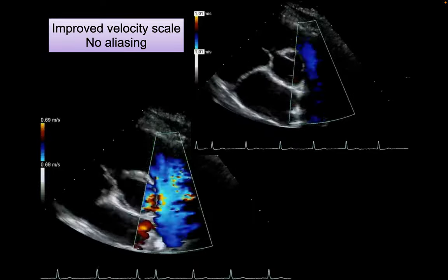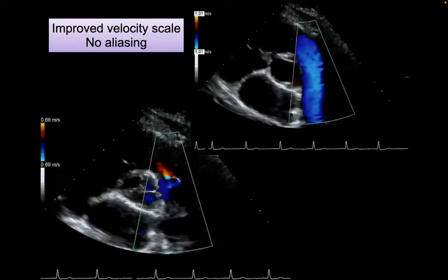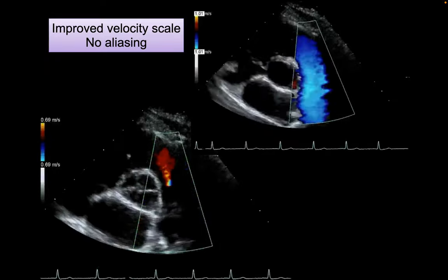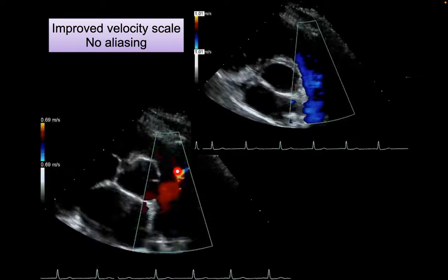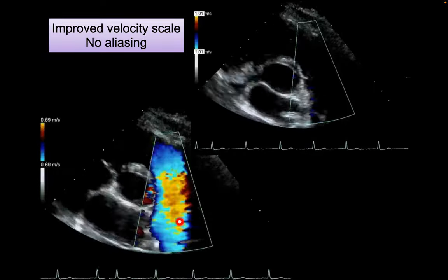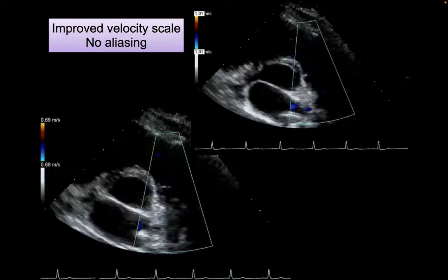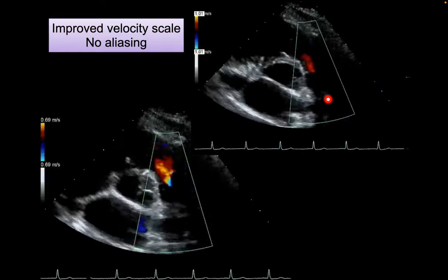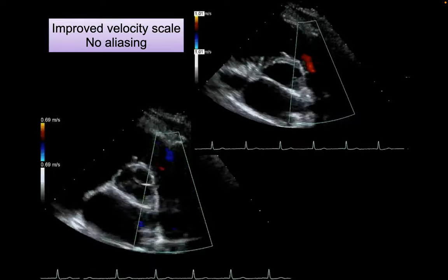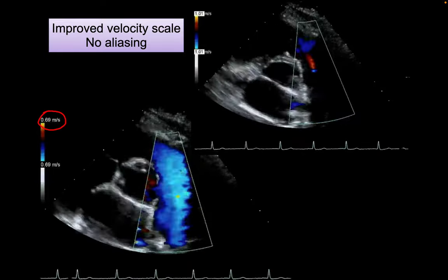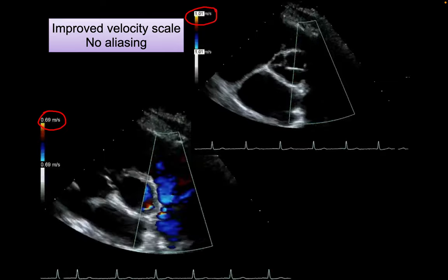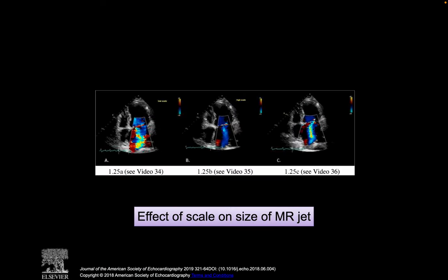So if you change your velocity scale, it may just get rid of all these ambiguous areas. So see how here it looks like there might be some aliasing and some turbulent flow, but in fact, it is not turbulent. It is a laminar flow. The only problem was that your scale settings weren't set right. If you don't set your velocity scale correctly, it will have a significant effect on how you're assessing various abnormalities.